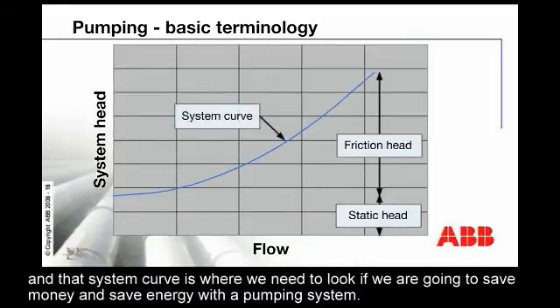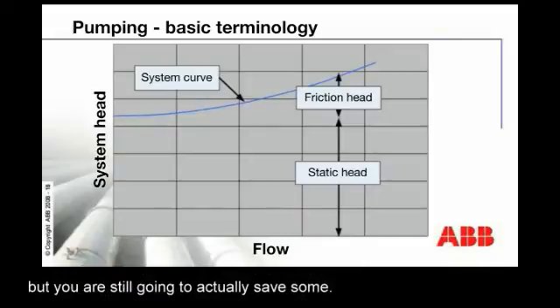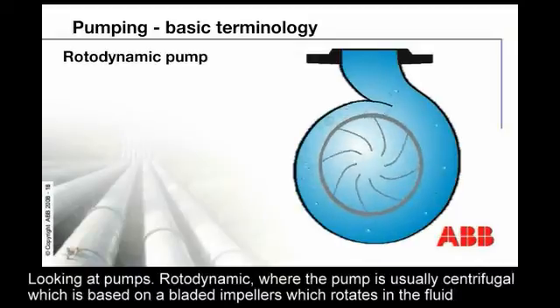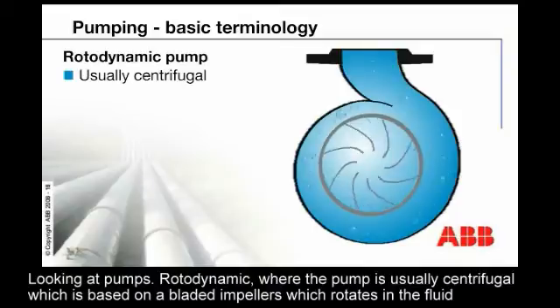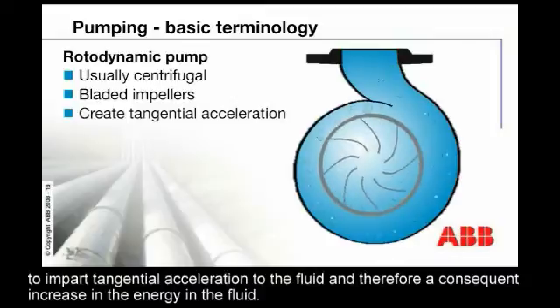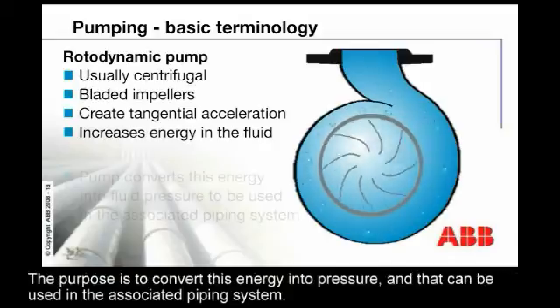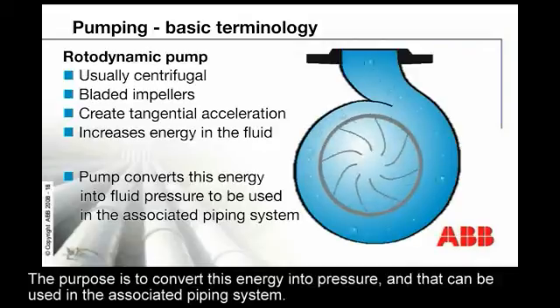That system curve is where we need to look if we're going to save money and save energy with a pumping system. Where the static head is relatively high compared to the friction head, there is actually less capability of saving money, but you're still going to save some. Looking at pumps, the rotodynamic, where the pump is usually centrifugal, it's based on a bladed impeller which rotates in the fluid to impart a tangential acceleration to the fluid and therefore a consequent increase in the energy in the fluid. The purpose is to convert this energy into pressure, which can be used in the associated piping system.